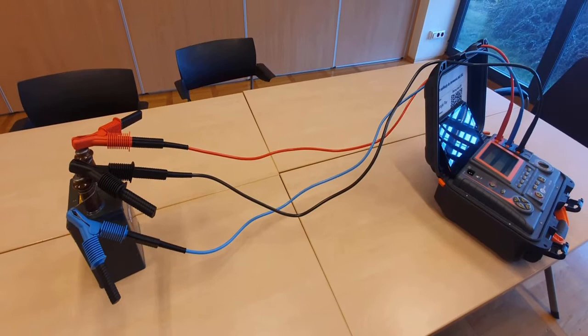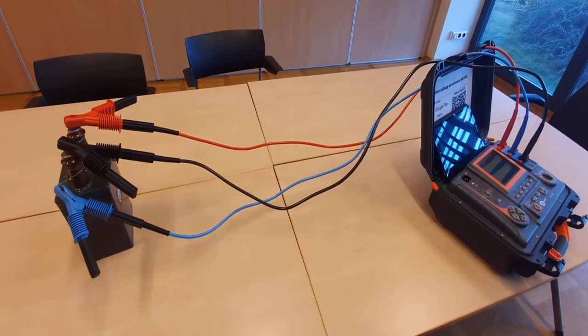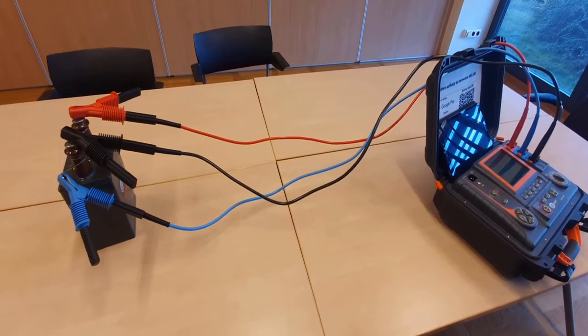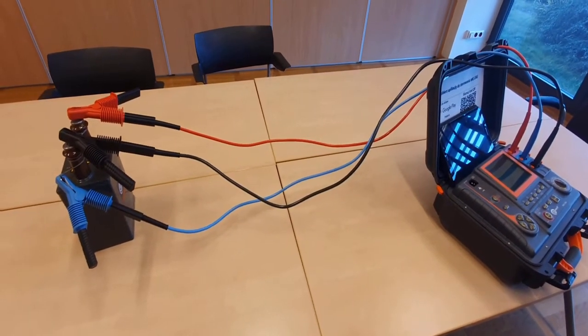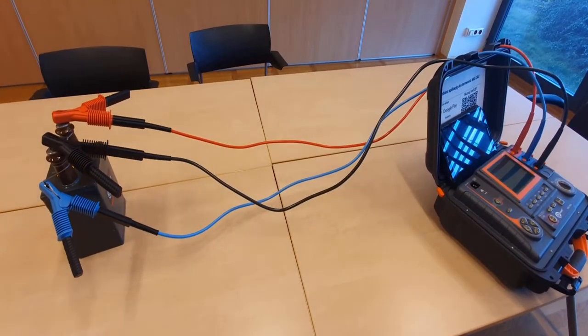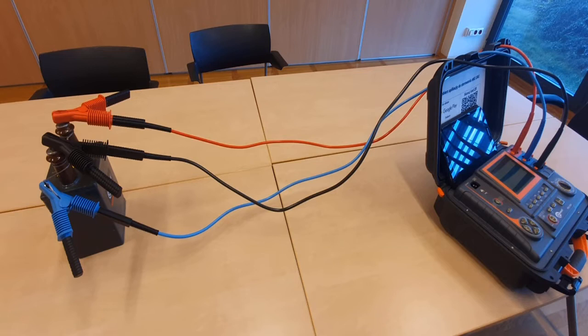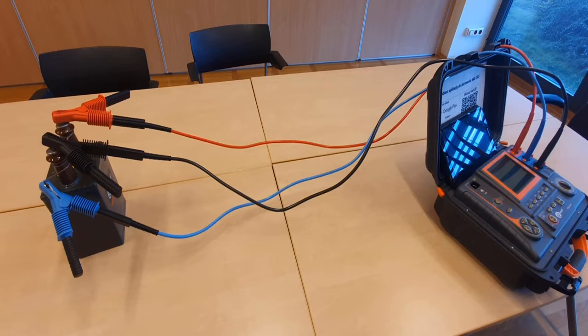Since we can measure the isolation resistance and check the results in giga or teraohms if it's okay. PDC is similar to measurement of the absorption coefficient. The absorption coefficient works very well for dry isolation, but for oil isolation they give failed results. So, it's much better to use the PDC method. The PDC measurement will show you whether the isolation is aging, if there is moisture due to the oil degradation or any bad process is happening, which could lead to some failure.